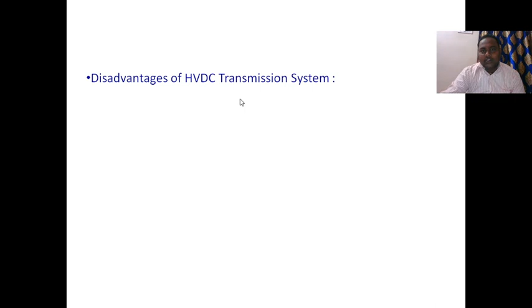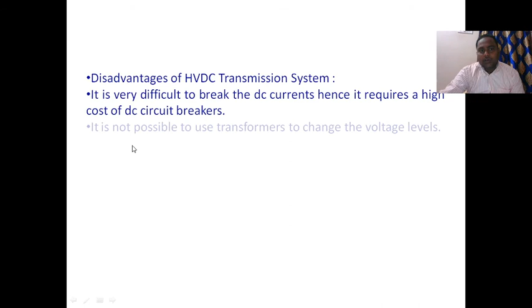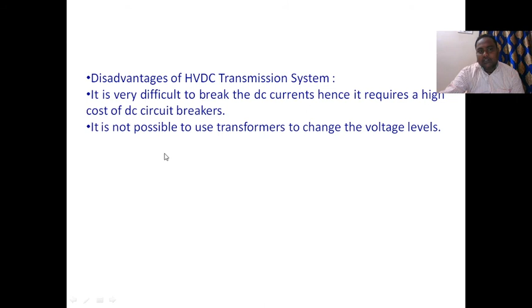Disadvantages of HVDC transmission system: it is very difficult to break the DC current, hence it requires high cost DC circuit breakers. Normally, AC circuit breakers work on the current zero phenomenon, but in case of DC there is no current zero phenomenon. The principle of operation in a DC breaker is different from AC circuit breakers. The cost of a DC circuit breaker is very much more compared to AC circuit breakers. It is not possible to use a transformer to change the voltage levels.